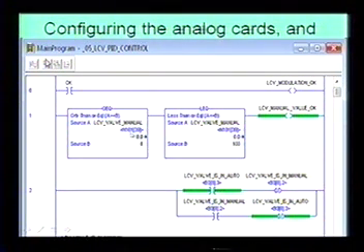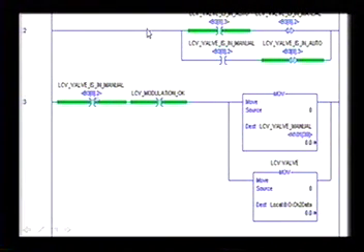So when I put N10:139, I can actually have something remote, a remote computer or a remote OIT actually control this value, and the operator would type in a number from between 0 and 100%. So if it is in manual mode and they type in 100%, it'll automatically move the output valve, the control variable, to 100% position. And you can see that here.